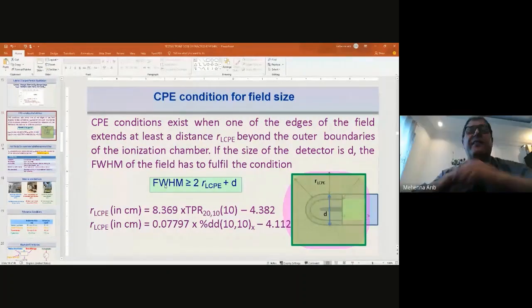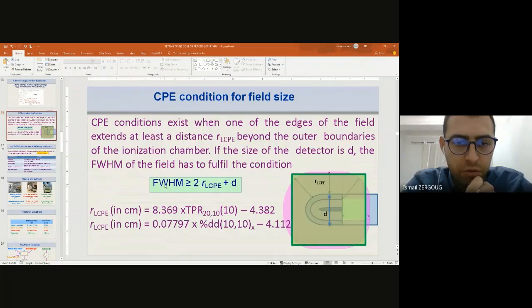Yes. Okay. That's why, for example, the farmer chamber: if you go to the farmer chamber, you will find that the maximum field size is 6 by 6, or something like this. You cannot go down. Another question: if you have, for example, a VMAT plan or IMRT plan, and you want to measure one dose point for the plan treatment, is there a specific chamber for that? Because we have a lot of small fields, and we can't know what is the smallest one that we can deliver by the plan. So what do you recommend as a chamber for measurement?